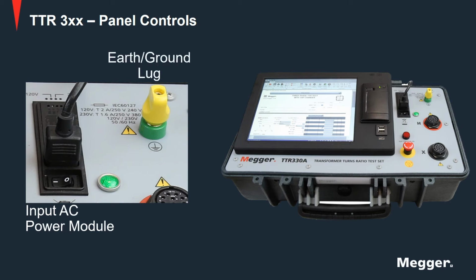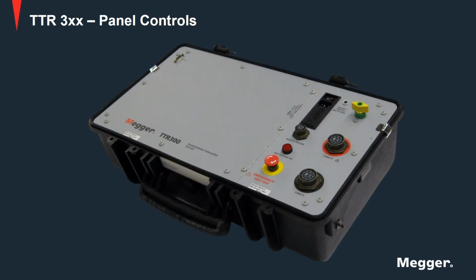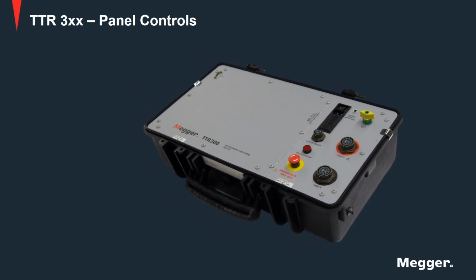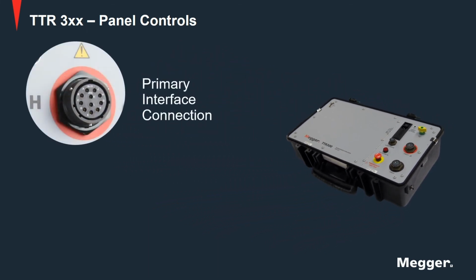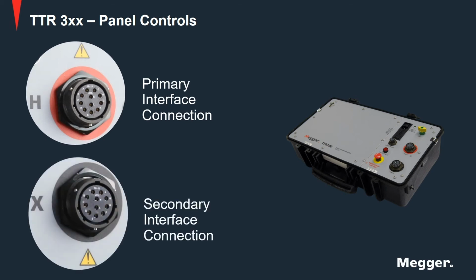Next is the earth ground lug. This connection is used to connect a transformer under test to earth ground for safety. The transformer and the TTR shall be at the earth ground potential when being operated. Next, we move on to the interface connections of the TTR300 series ratio meter. First is the primary interface. This connection has all the interfaces required to connect current and voltage inputs from the primary winding of the transformer into the TTR300 unit. Next is the secondary interface.